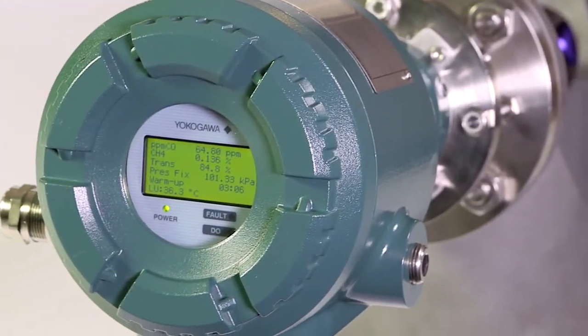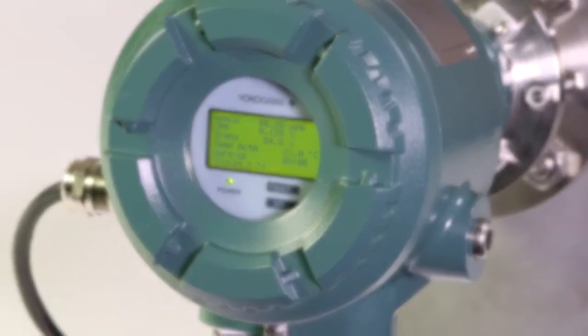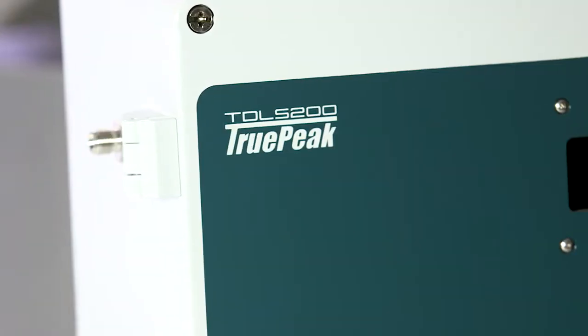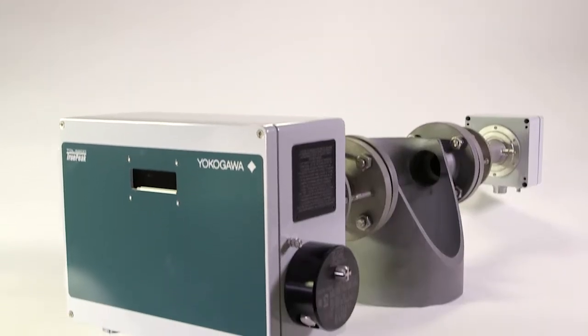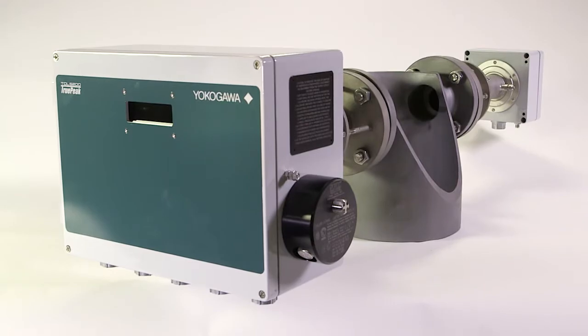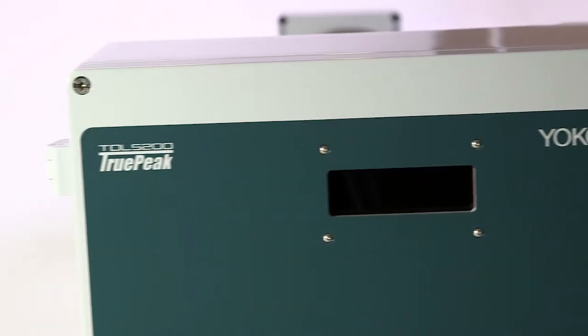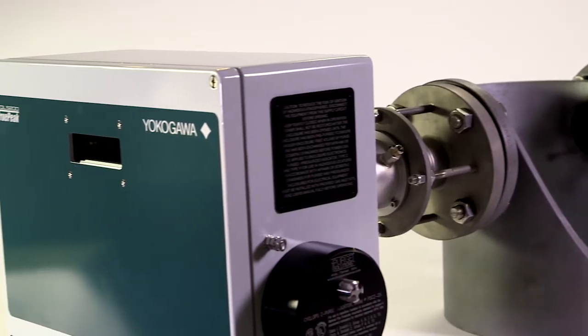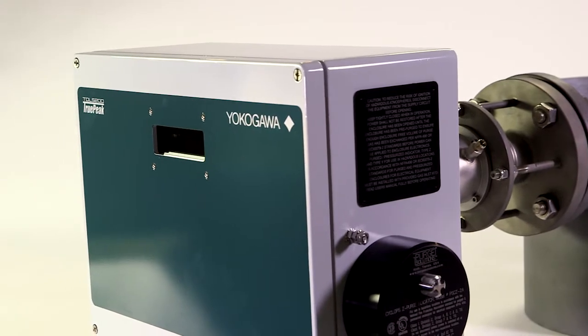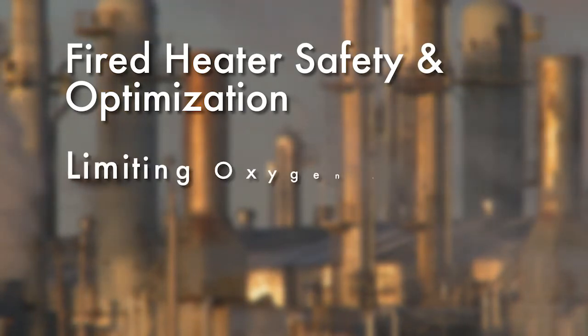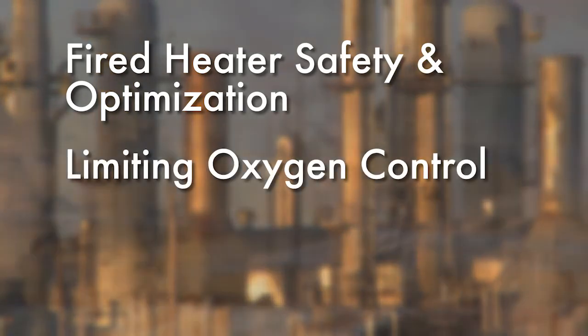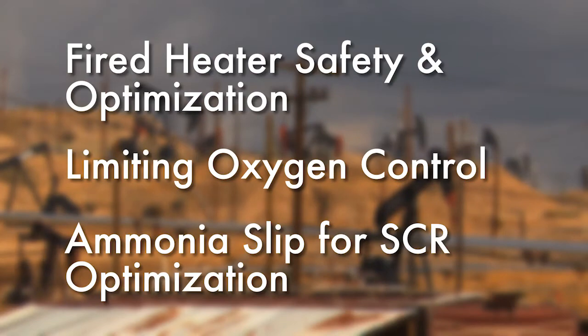to give our customers their most needed features combined in one analyzer, enabled by TruePeak technology. The original Yokogawa TDLS 200 gas analyzer platform was the first tunable diode laser spectrometer designed with the flexibility to be applicable to most industrial processes, including fired heater safety and optimization, limiting oxygen control, and managing ammonia slip for SCR optimization.